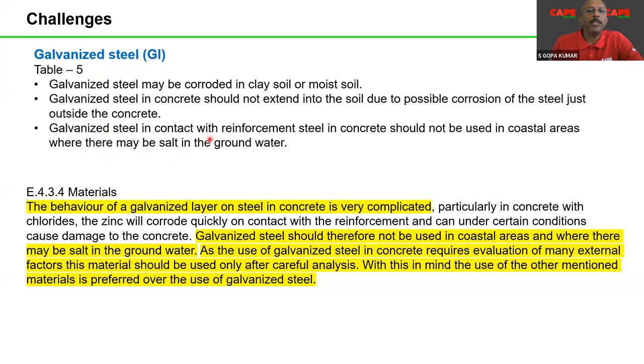The last one: galvanized steel in contact with reinforcement steel in concrete should not be used in coastal areas, because if you put a GI inside the concrete, it will corrode faster. So GI cannot be used in soil because of corrosion. GI cannot be used in coastal areas or in places where you have salt water, you will be in trouble. And these comments, you are supposed to read and understand.